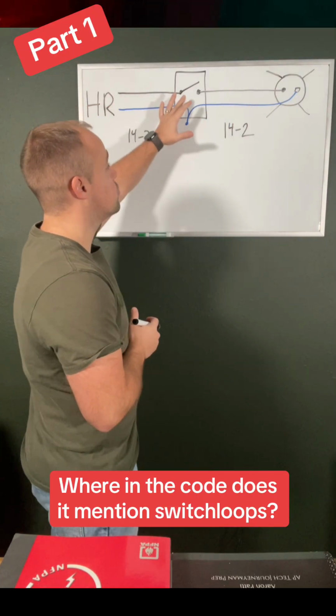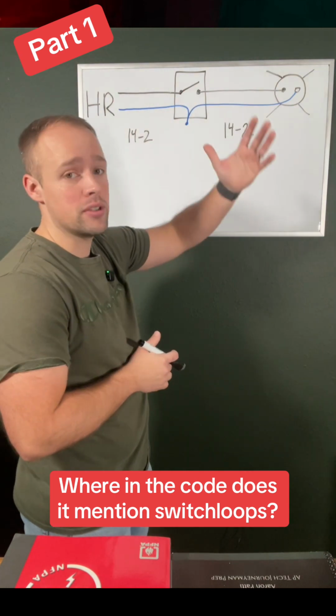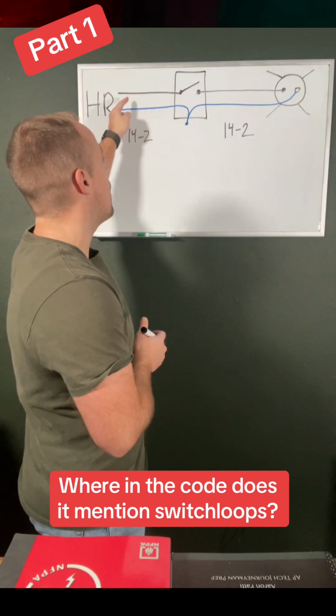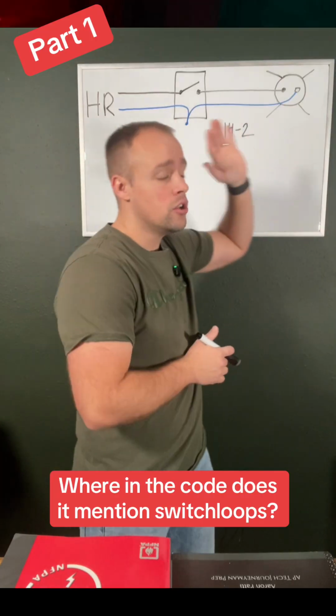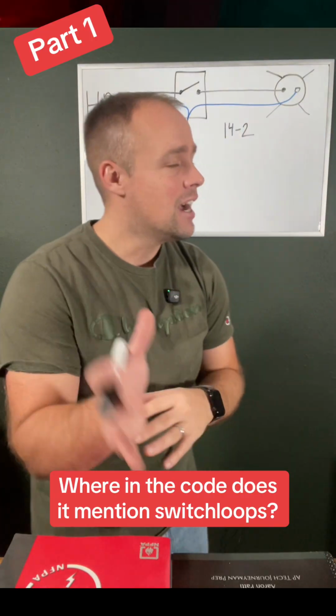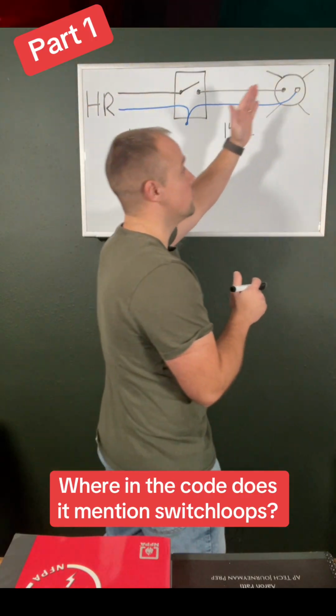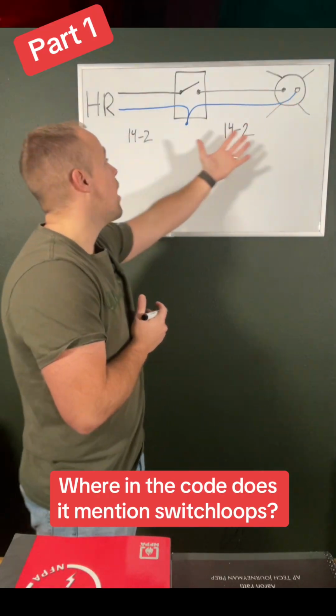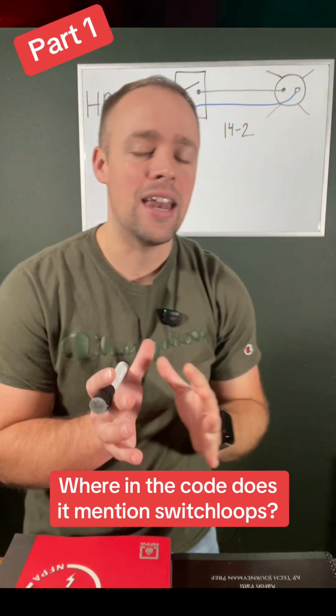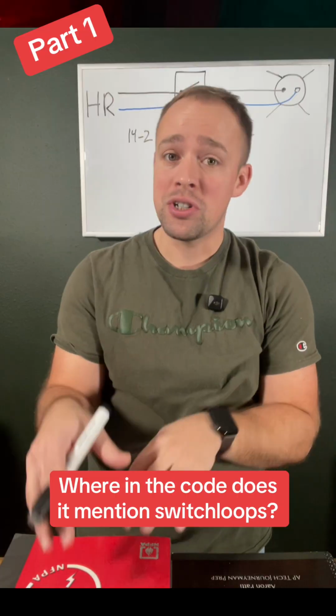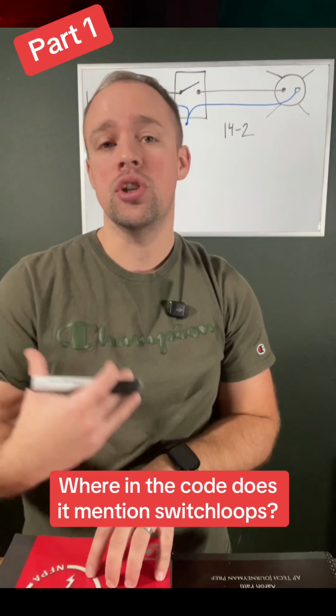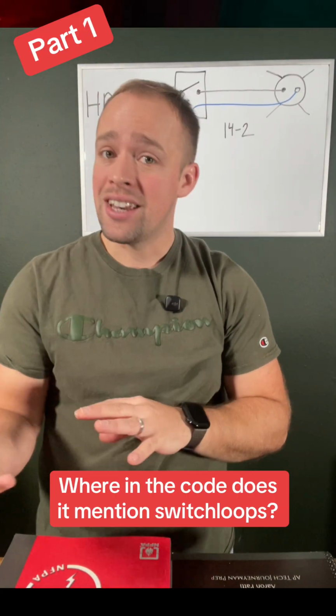As you can see, the switch, when it goes to the on position, it closes that circuit, allowing power to travel through the switch to the light. And again, in theory, electricity travels on the ungrounded conductor to the load, in this case it's a light, and then it travels back on the neutral. But again, for a switch loop application, which the code does allow us to use, it's going to be wired different, and let me show you how.